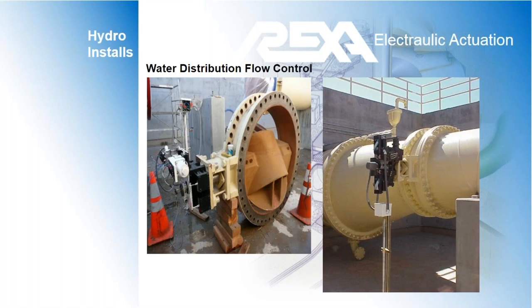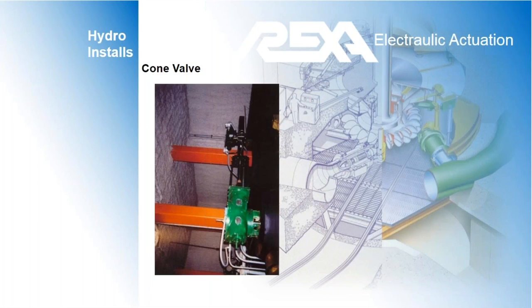This particular unit uses a double motor design, allowing for twice the speed, and if needed, redundant motor functionality for water distribution flow control. For some applications, such as cone valves, there can also be slow control for opening and closing the discharge of water. Two-speed function is available as a standard feature and can be enabled. Two-speed can be set up either for stroke direction or change the speed when a set point has been passed.